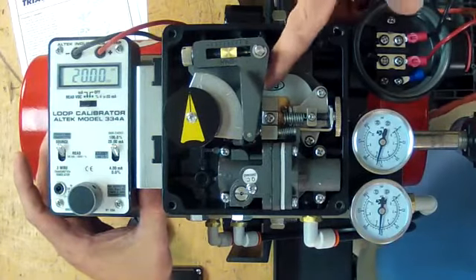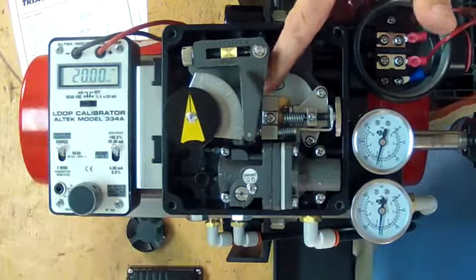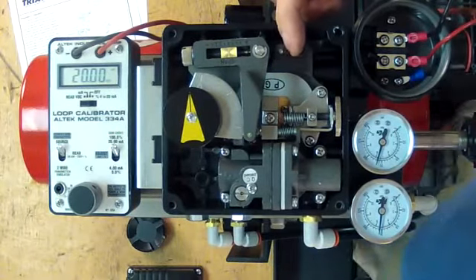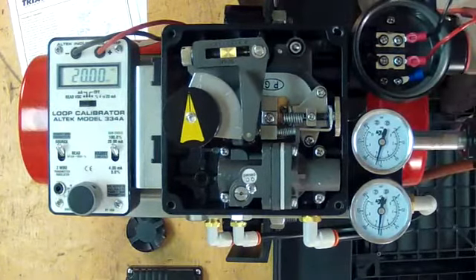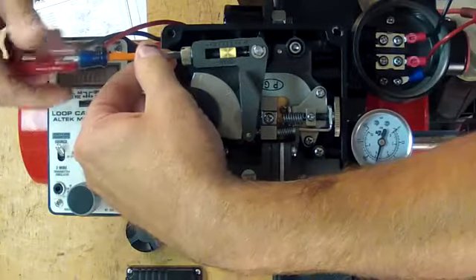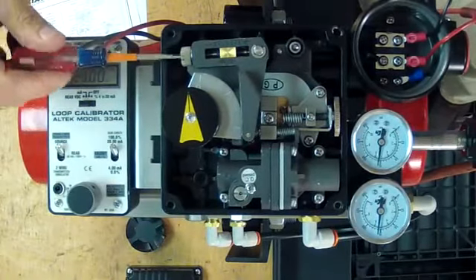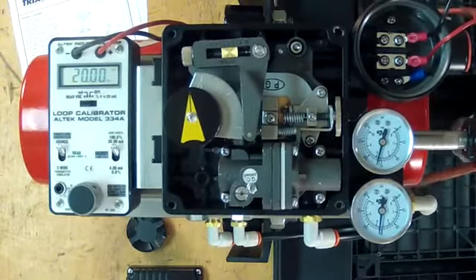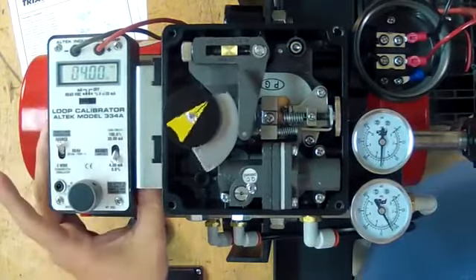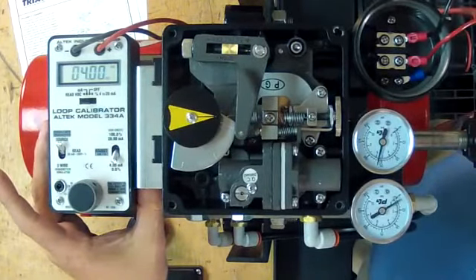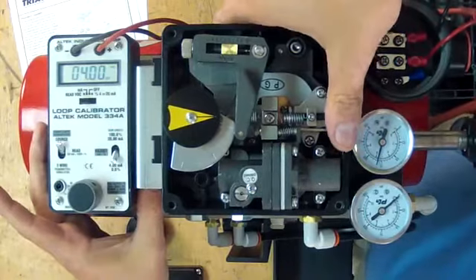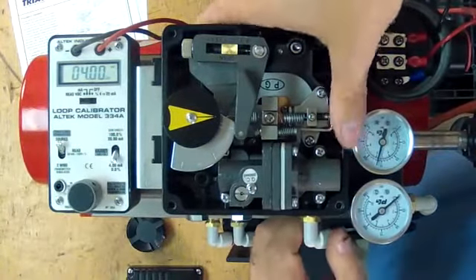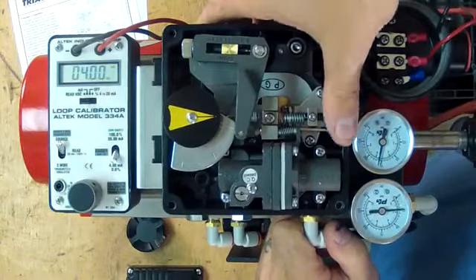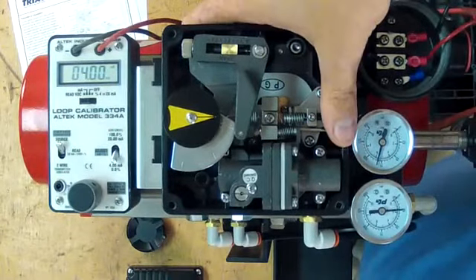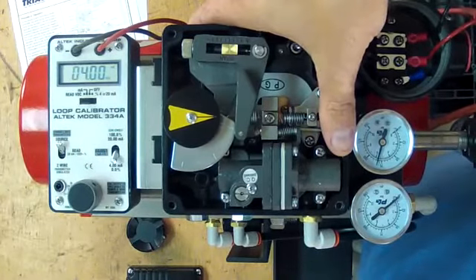Now I'm going to pull the counterbalance towards me to see if any air bleeds off, which it did, meaning you need a little more span in this to fully load the actuator with air for your open position. So now you're going to turn the screw counterclockwise towards the plus sign, maybe a turn and a half, and back down to our 0 or 4 milliamps. Same as before, clockwise till the gauge climbs. Back it off till it goes to 0 nice and easy. Back to 20.